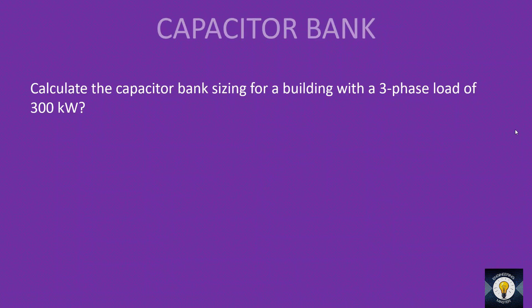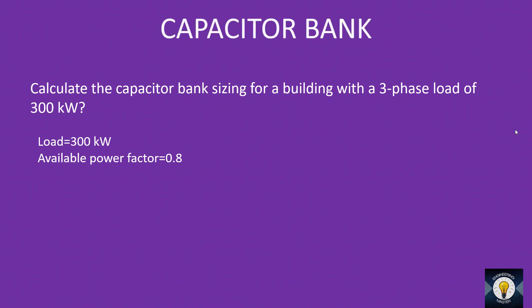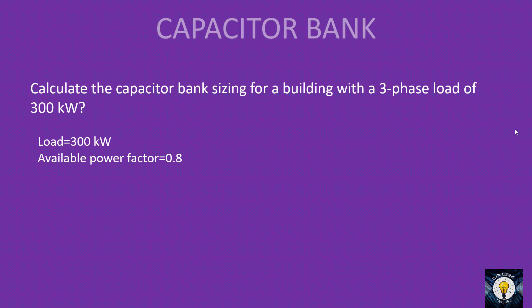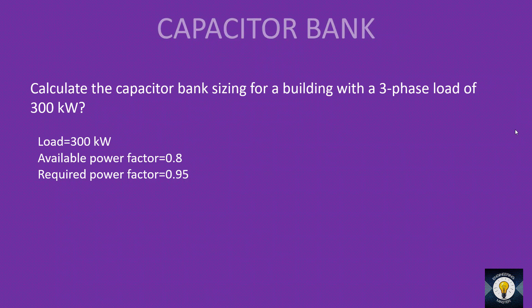Let us learn capacitor bank sizing. Calculate the capacitor bank sizing for a building with a three-phase load of 300 kilowatt. Our load is 300 kilowatt. The available power factor — if not specified, consider it as 0.8. The required power factor — anything between 0.95 to 1 is considered a good power factor, so we set the required power factor to 0.95. We are lifting the power factor from 0.8 to 0.95.